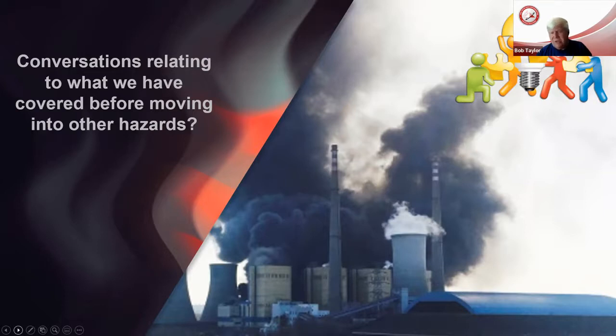In those cases, a nuclear plant has similarities to most other facilities in having Class B fire hazards. Many of them are going to be two- and three-dimensional fires that foams will not effectively control, and dry chemical and others will not. Same with transformers - there are atomized droplets of combustible liquid becoming airborne, the vapors, ignition. So my point is that there are similarities, and one of the greatest similarities is dealing with transformer hazards as well as lubricating oil hazards.